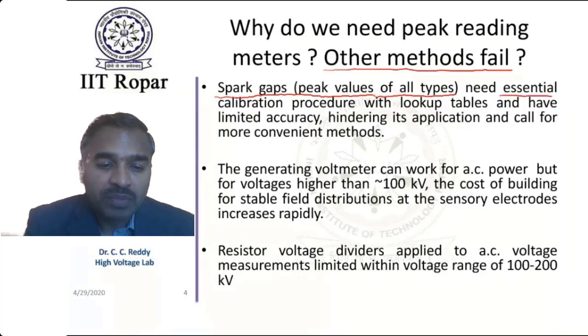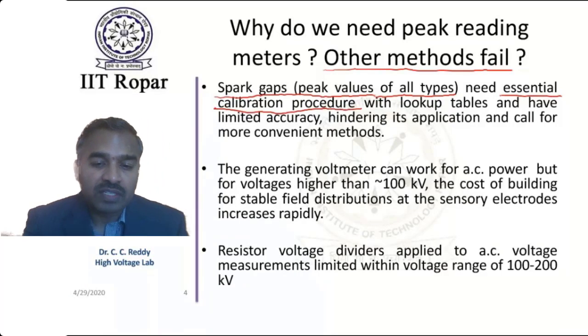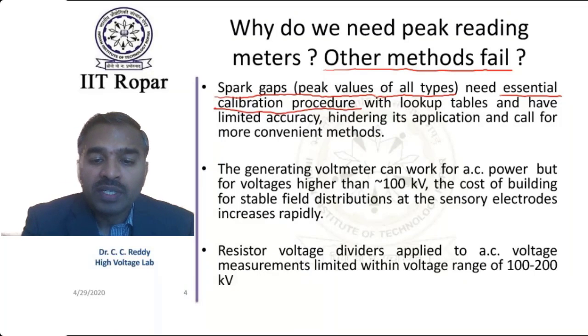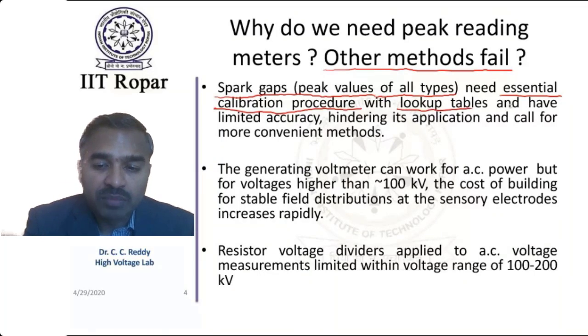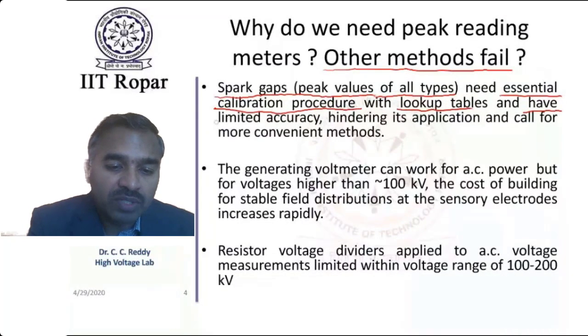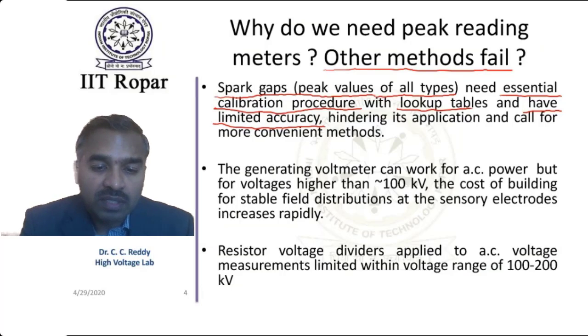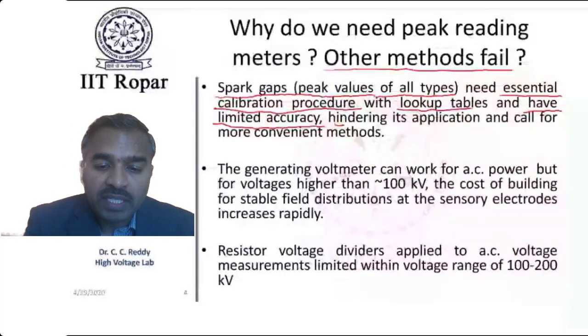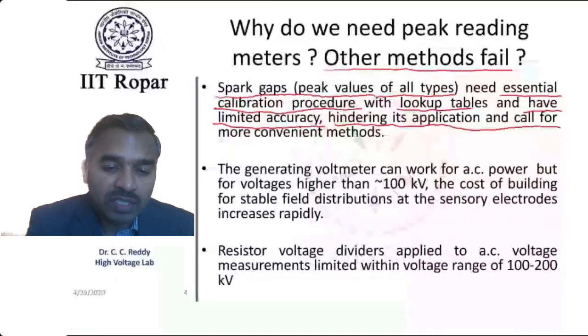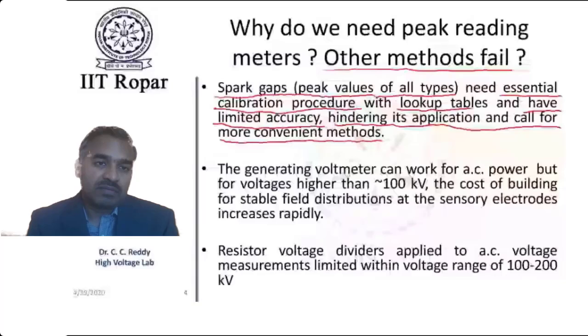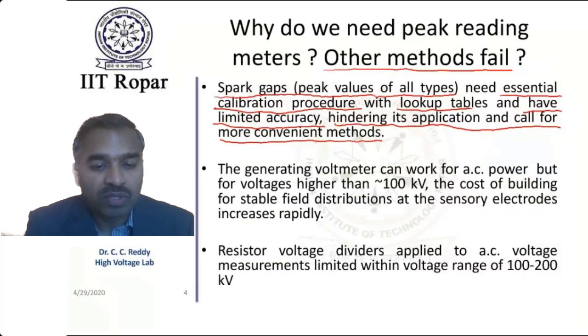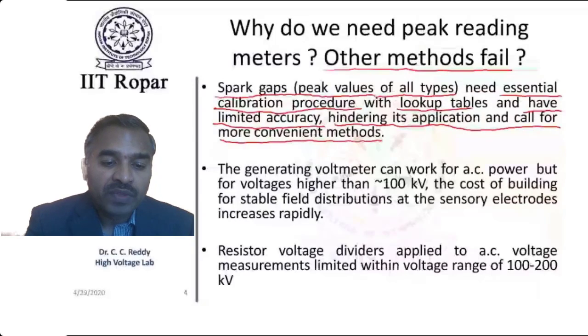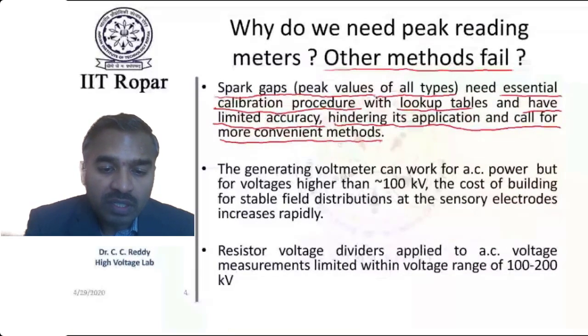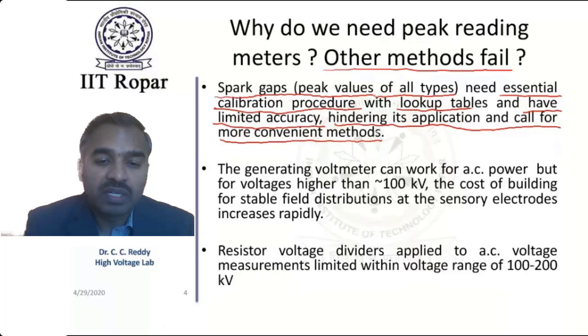But they need calibration, various correction factors for atmosphere, and lookup tables. It is a cumbersome procedure, and at the same time they have limited accuracy. Accuracy is not 100%. So this aspect hinders their application in day-to-day use. We need more convenient methods to measure the peak voltage. Of course, spark gaps will be used for calibration, but for day-to-day measurements we don't need cumbersome procedures like that. So peak voltmeters are needed.